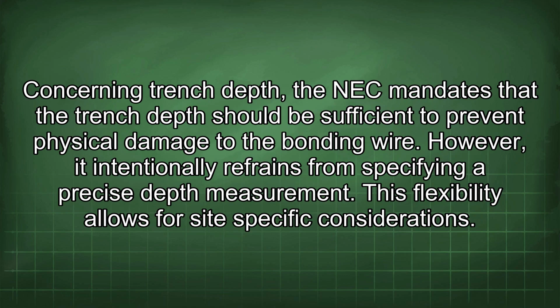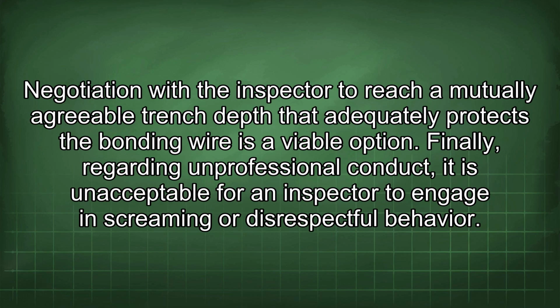Concerning trench depth, the NEC mandates that the trench depth should be sufficient to prevent physical damage to the bonding wire. However, it intentionally refrains from specifying a precise depth measurement. This flexibility allows for site-specific considerations. Negotiation with the inspector to reach a mutually agreeable trench depth that adequately protects the bonding wire is a viable option. Finally, regarding unprofessional conduct, it is unacceptable for an inspector to engage in screaming or disrespectful behavior.